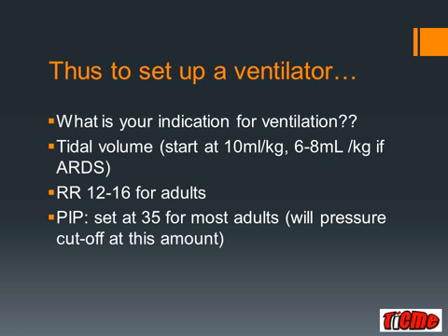On most ventilators, you need to set a cutoff for the peak inspiratory pressure. Now, hopefully we won't be ventilating our patient to this pressure, but the machine will stop ventilating if it reaches this number. 50 centimeters of water is probably the amount where barotrauma will happen in most adults. I like to set it at 35 to 40, just so I'm aware that pressure's arriving to potentially dangerous levels.